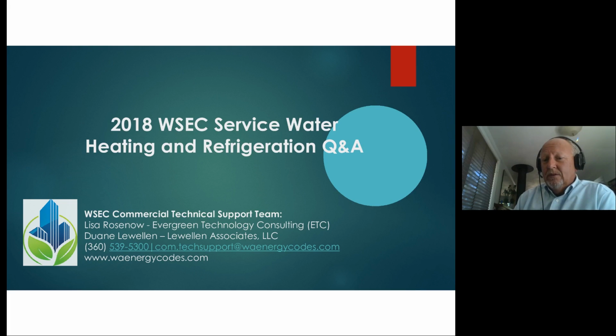Yeah, I would agree with that assessment. Okay, so Derek has a question. For heat pump water heater COP, what ambient condition is that rated at? There are two different things there. If it's a tank type heat pump water heater that's regulated under the efficiency tables with an energy factor, there are very specific conditions. If it's a commercial type heat pump water heater, the code does define what those conditions are for the COP. I'm trying to look it up right here real quick. With an air temperature of 60 degrees or less. So 60-degree outdoor air temperature for those commercial, what we'll call split system type water heaters.